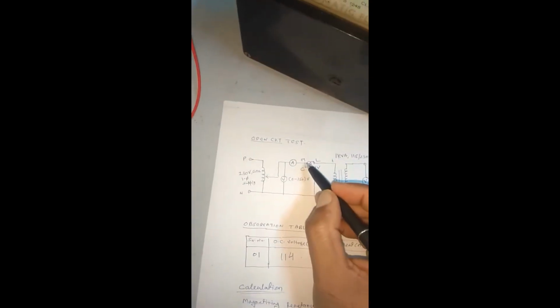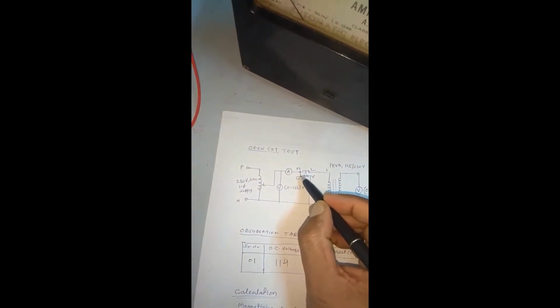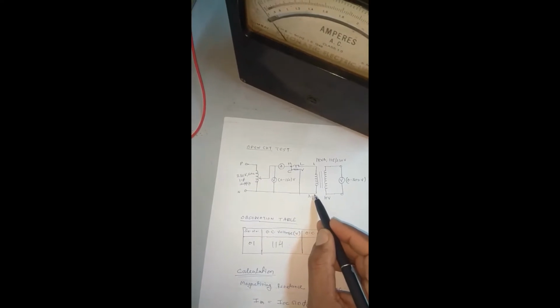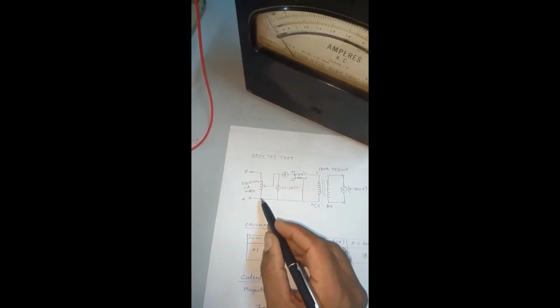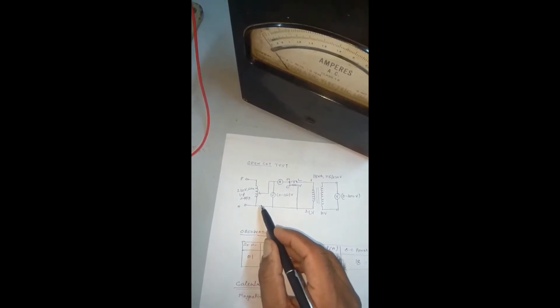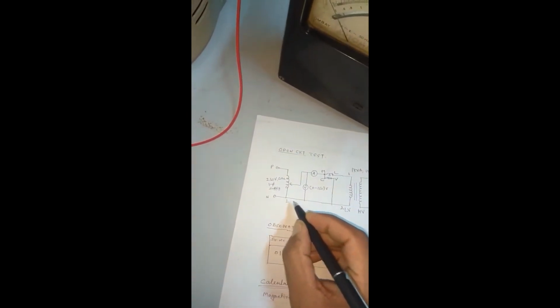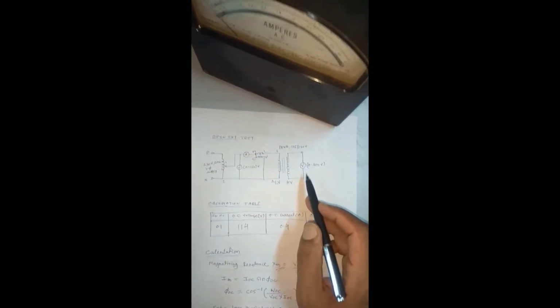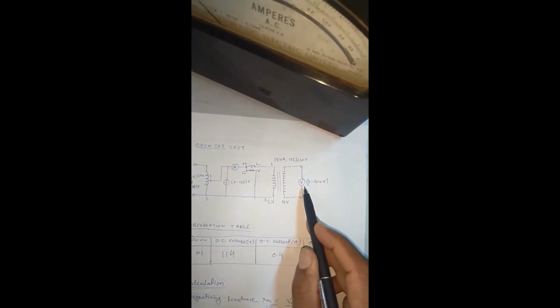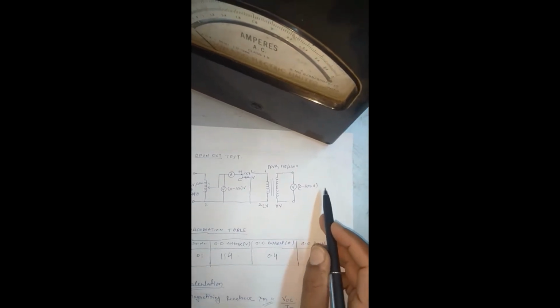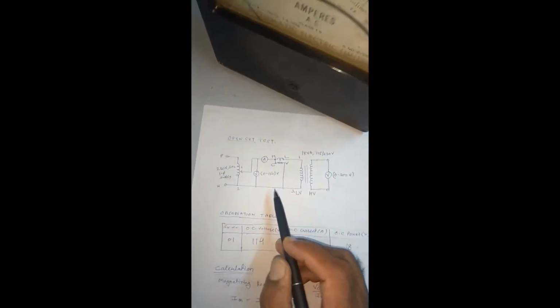You can see that M and C are shorted, so we will short them with a connecting wire. Then the second terminal of LV is connected to the other terminal of the dimmerstat. We can mark it as 2, and the first as 1. The HV is kept open. If we want to measure the voltage across HV, we can connect a voltmeter of range 0 to 300 volt, and here the range of the voltmeter is 0 to 150 volt. So this is the connection diagram.